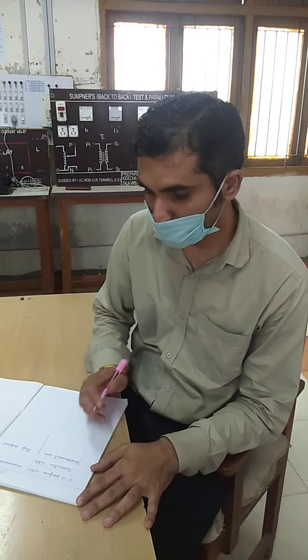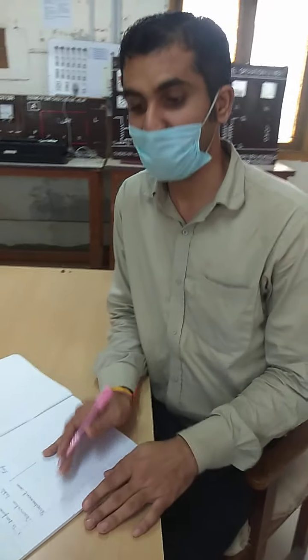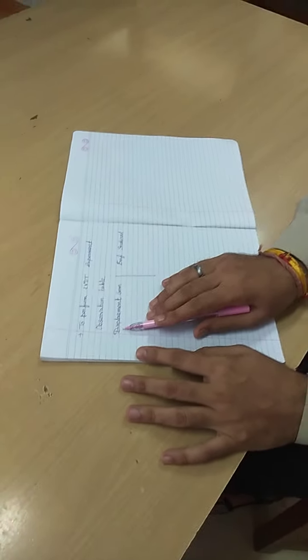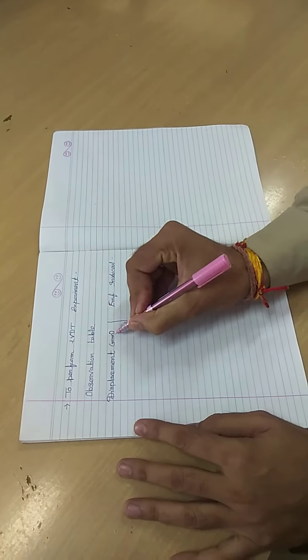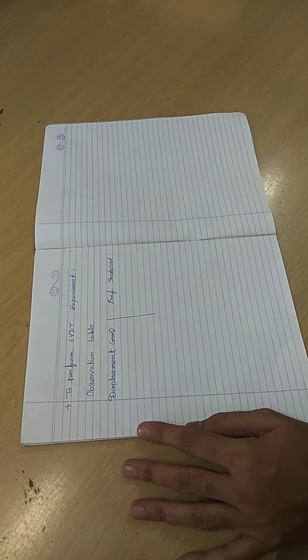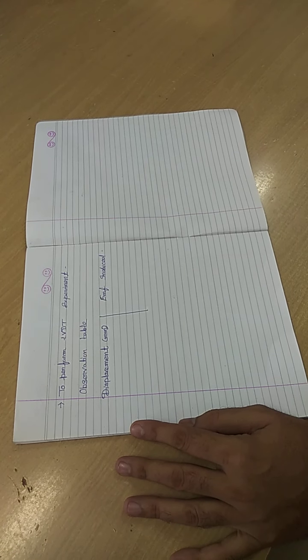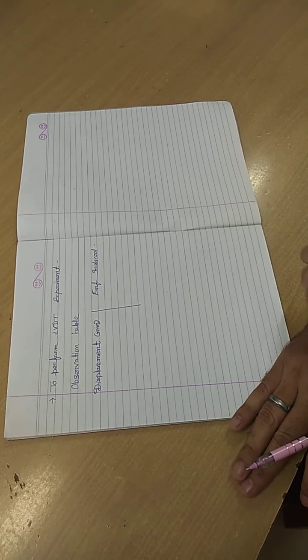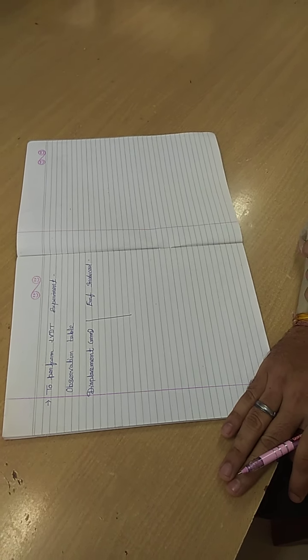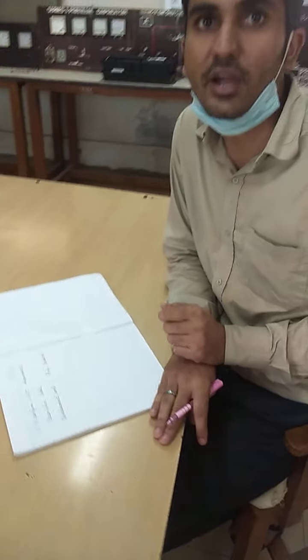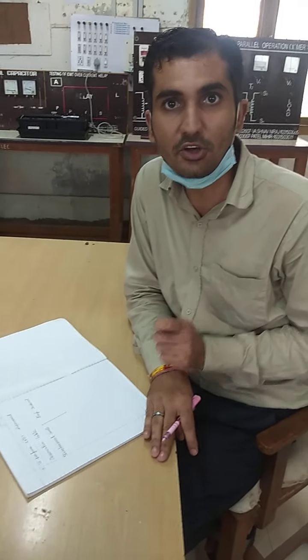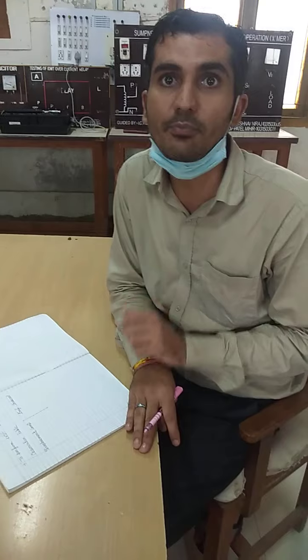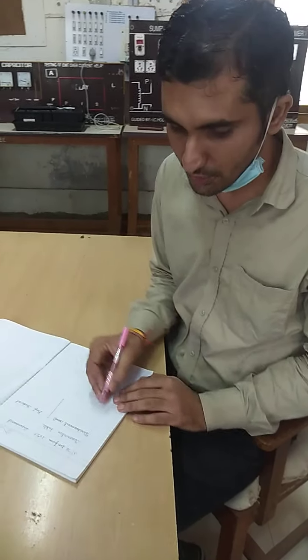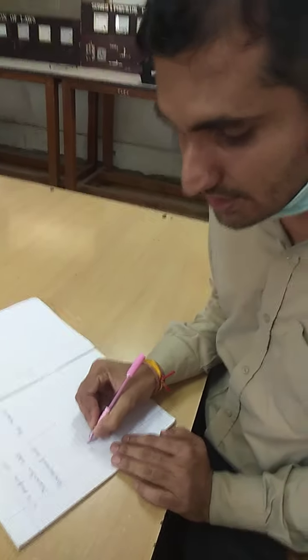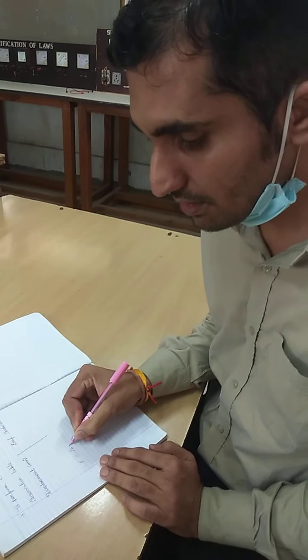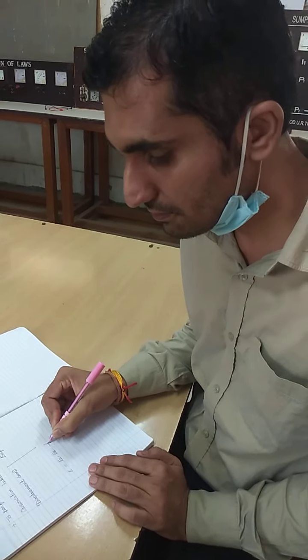So we will directly go to perform the practical in which we will measure two values: displacement of the core in mm, and EMF induced in the secondary winding. The EMF induced in the secondary winding depends on the algebraic sum of the two coils, because both secondary coils are connected in series opposition. So it will give the result equal to EA minus EB.